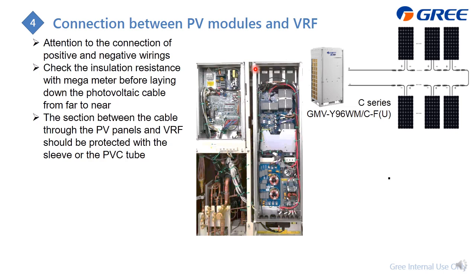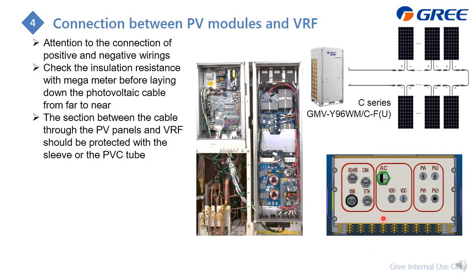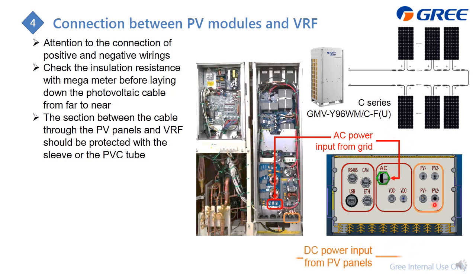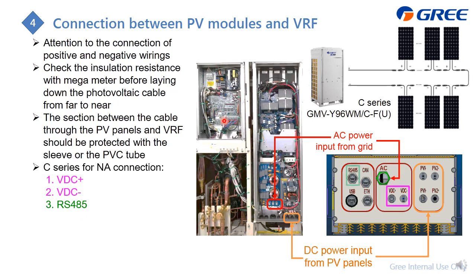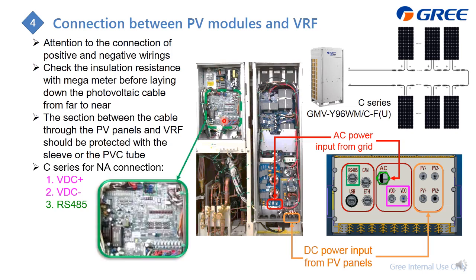And here, this is at the bottom side of this one. So you need to connect the AC power to here, which is through this hole. And from the PV panels, you can connect directly to here. And also, as the converter is separated from the outdoor unit, you need to do the wiring, which is the VDC to here, and also the RS485 to here. And the other end is already connected on the outdoor unit, which is here. This is RS485.